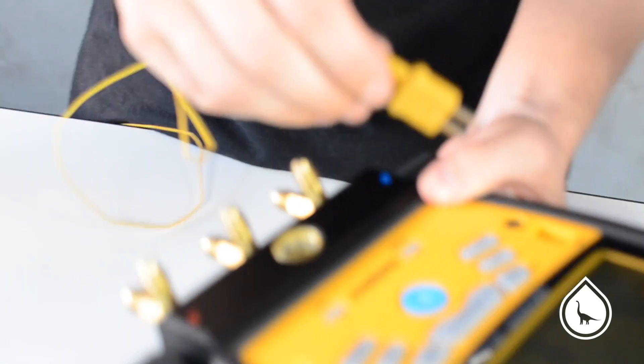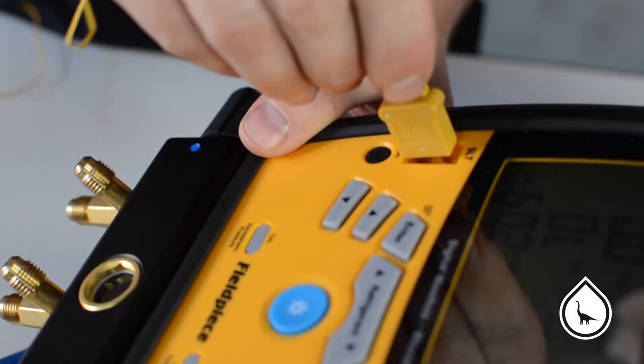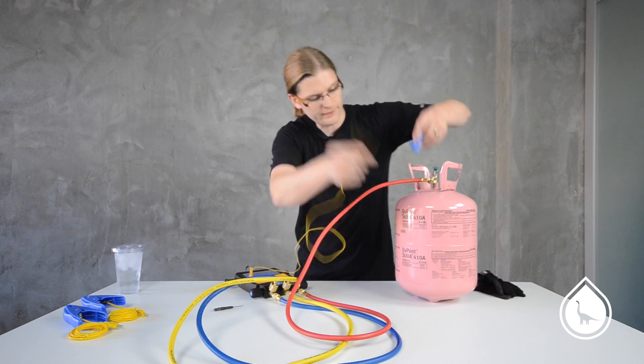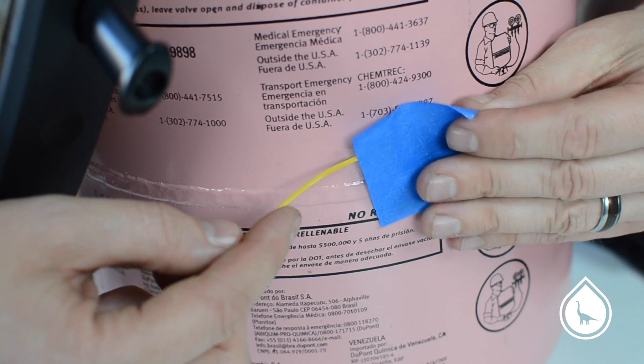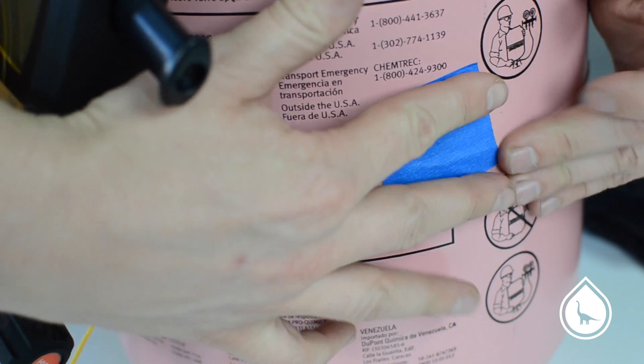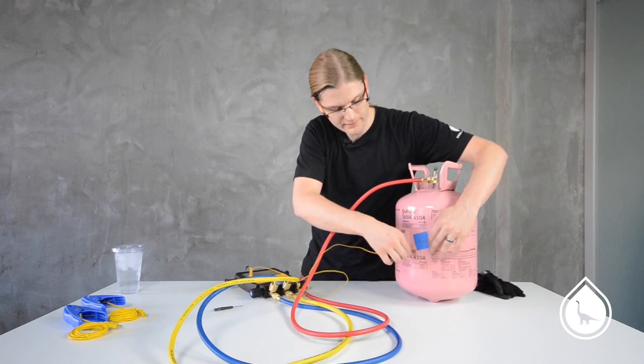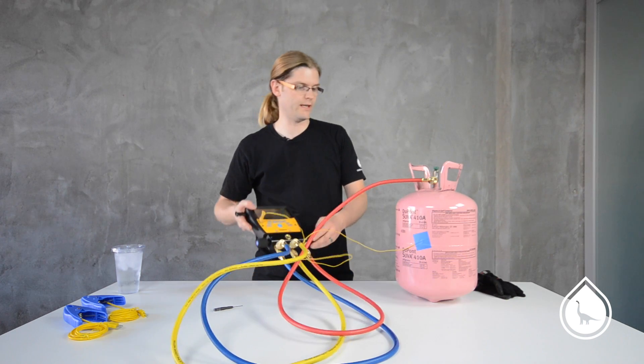All right, with it connected to the tank, we can now hook up our thermocouple. It goes on the suction line temperature side, and then the thermocouple itself gets connected to the middle of the canister. Try to stay away from the weld a little bit because it can throw off the temperatures, but stay in the middle of the tank as much as you can.